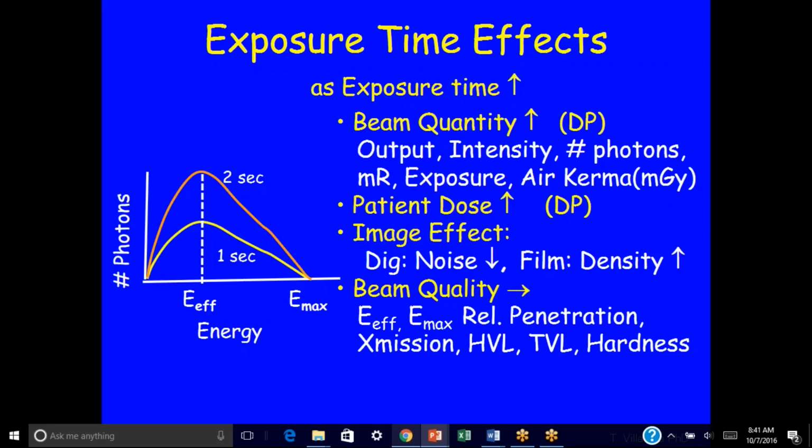If you take a filter in your hand and you stick it inside of an X-ray beam, question, how much does that filter reduce the intensity of X-rays? The thicker that filter, the less penetration you have, the less transmission you have, more of it will be absorbed within the filter. Well, how thick must that filter be to reduce the beam down to 50% of its original value? That's the HVL. A cousin, a related measure is a TVL, tenth value layer, the thickness of material required to reduce the intensity of a beam down to 10% of its original value, 1/10 of the original value.